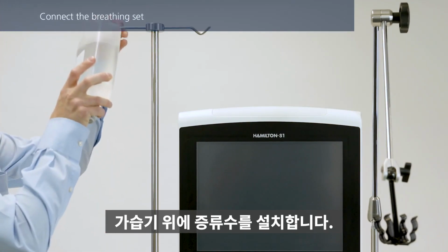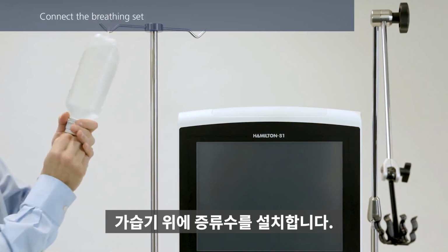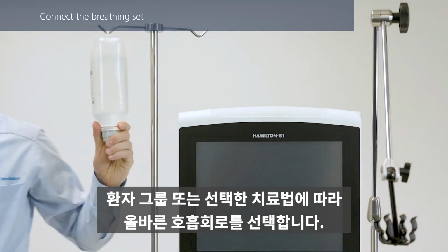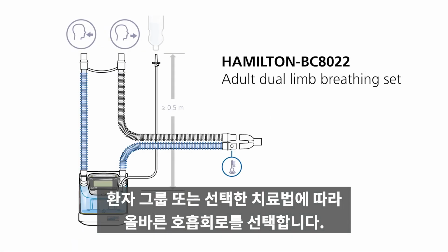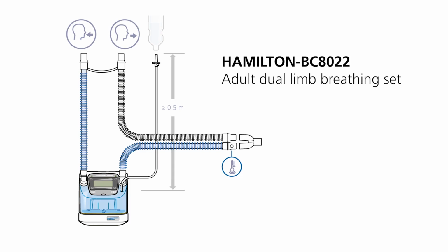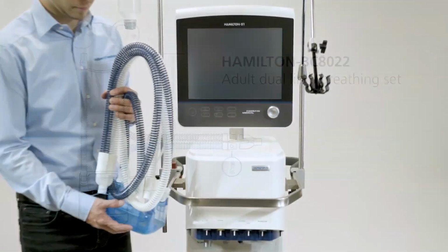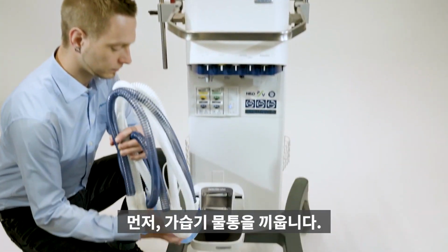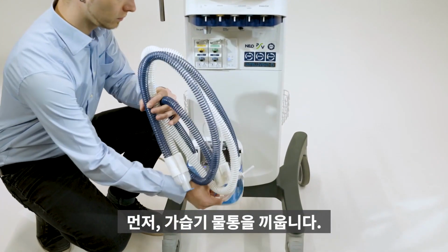Install a water bag or bottle above the humidifier. Choose the correct breathing circuit according to the patient group or selected treatment. The following information applies if you are using the Hamilton BC8022 breathing circuit or any other double-limb heated breathing circuit. First, insert the humidifier chamber.